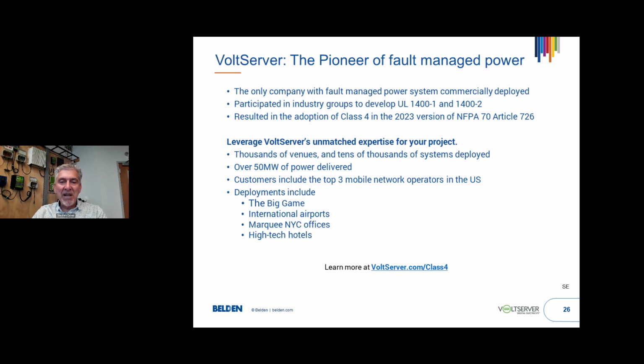From the VoltServer side, we've seeded the ground with thousands of installation points and about 50 megawatts of installed power now. Each of those facilities, when you see a farm or a stadium, is often hundreds of kilowatts and sometimes megawatts of installed power. We currently focus on big stadium installations, airports, offices, hotels, and newer areas like EV charging and indoor farming. Really, the world's the oyster on this stuff, for everybody, not just VoltServer. It's an improved way to install power.